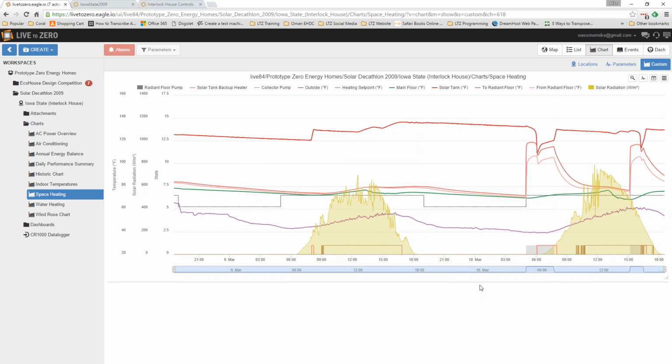And then what happened is that the building heated up, and here it didn't take too long for it to start heating up. And then it heated up all the way to 72 by 7 a.m., 7:15, which is actually before they even show up, the occupants. But by the time they got there at 8, the temperature was 72.8, which means that the building is already heating up from the sun.